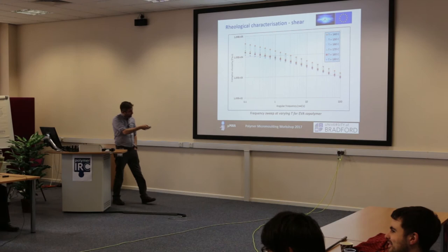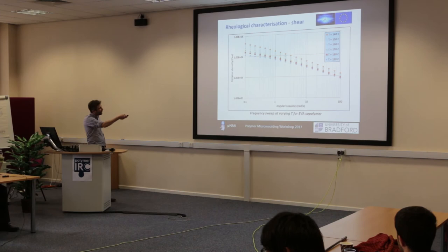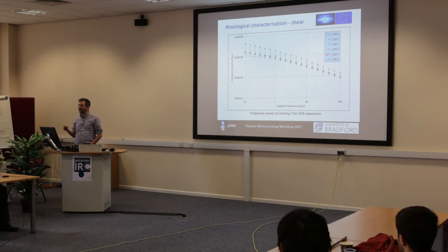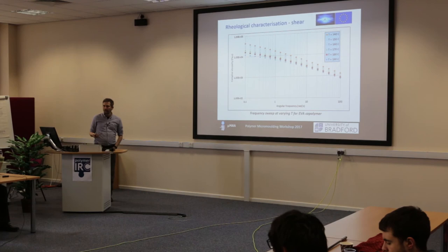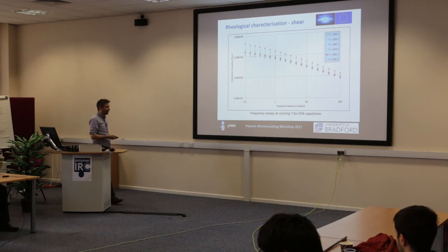By the time you get to 100, which is pretty much the limit of what we can do on these rheometers, we are down at about 1,000. So that's a 40-fold decrease in the viscosity simply by shearing it, okay? Which is huge. And we can play around with that to a large extent in order to give us exactly what we want. So there's increasing temperature. Clearly, the higher temperature, the less viscous the material is going to be.